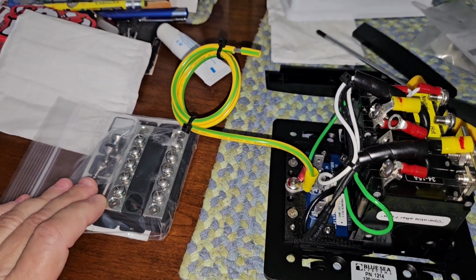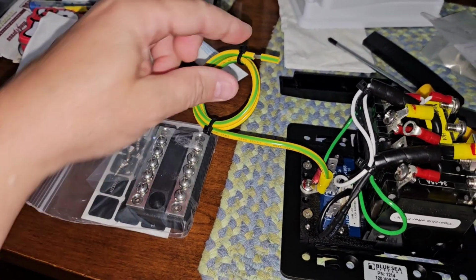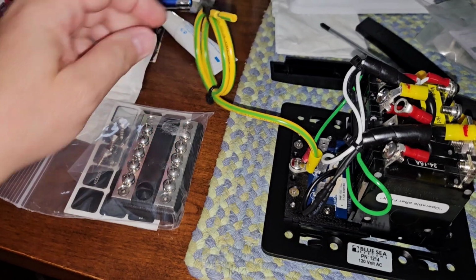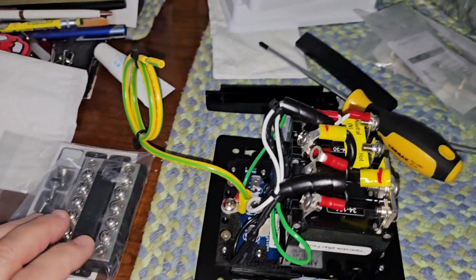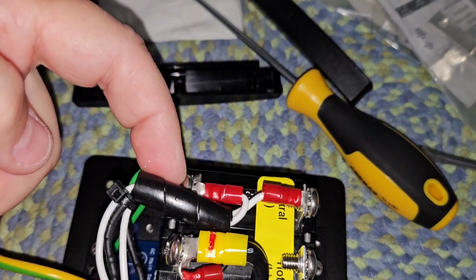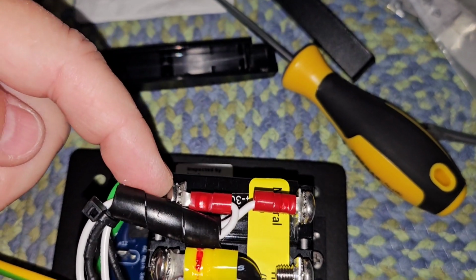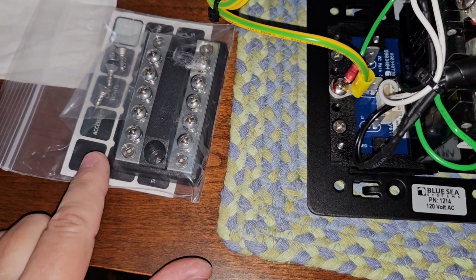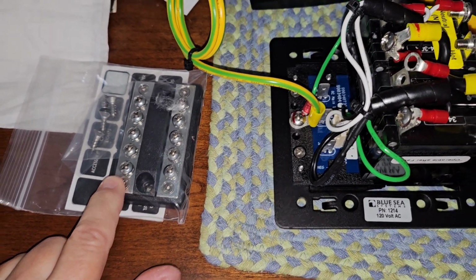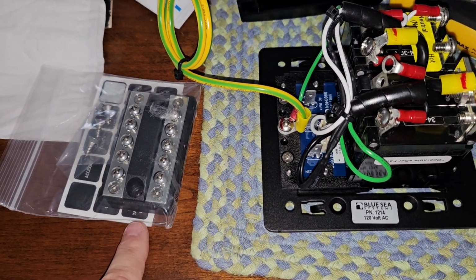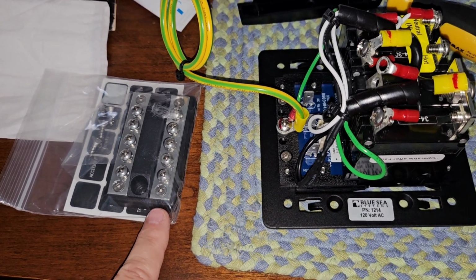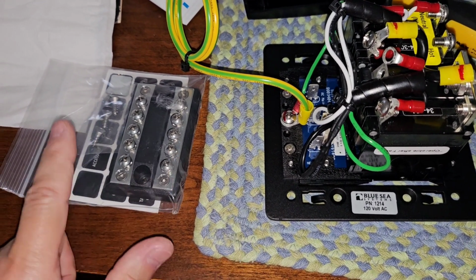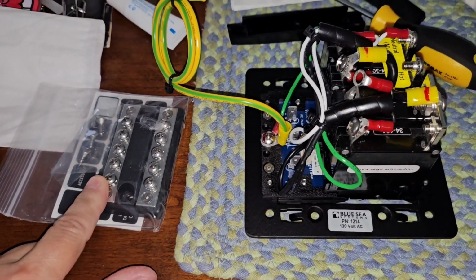Bottom line, I'll have two bus bars: one for the ground, which this is, and one for the neutral. The neutral comes off this terminal, off the circuit breaker, to create a neutral bus and a ground bus, which is where I'll connect my circuit wires.